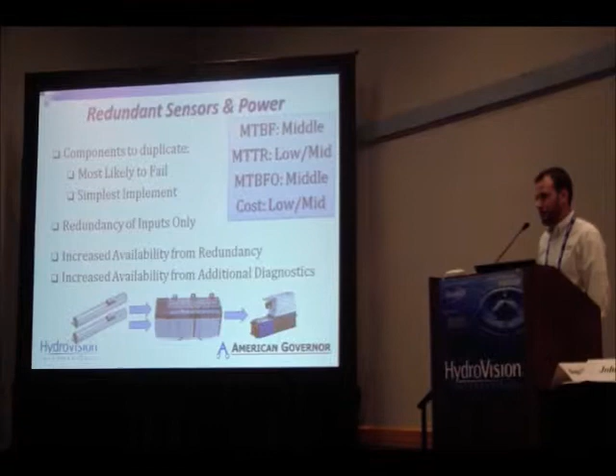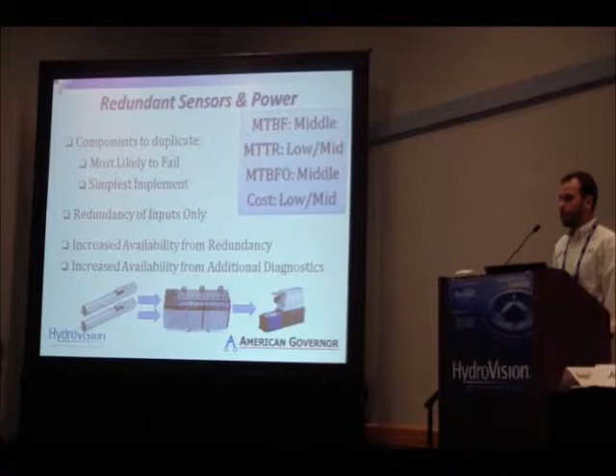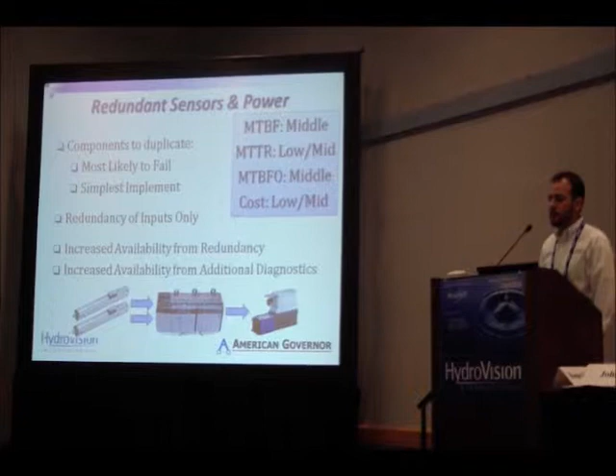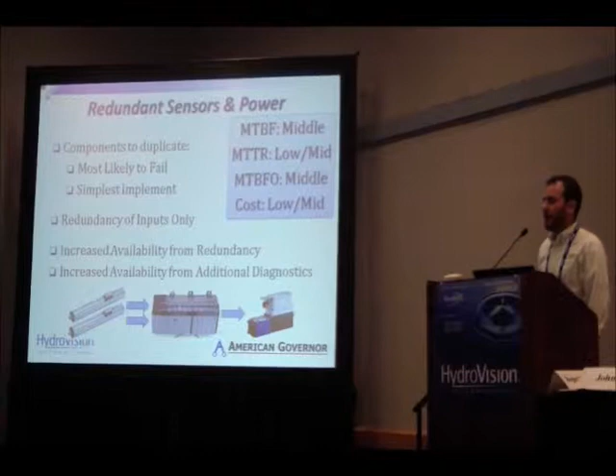all, just monitoring. Inputs are a little more complicated, but not much. You can bring 2, 3, how many pressure transducer speed signals into your controller, have a high signal select or voting algorithm, choose a single best signal, and then the rest of your system remains unchanged.